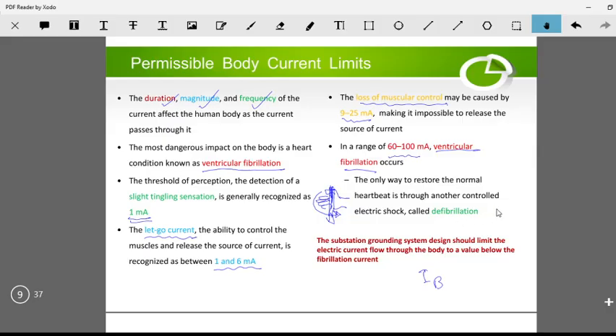That's what happens when different amounts of body current flow through your body. So you have to make sure that the current going through the body, even in fault conditions in a substation, is below a certain limit, at least below 6 milliamps or so, you still can let it go. If you go beyond this level, it will create a catastrophe.